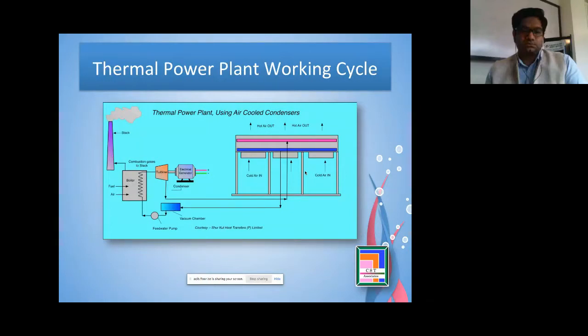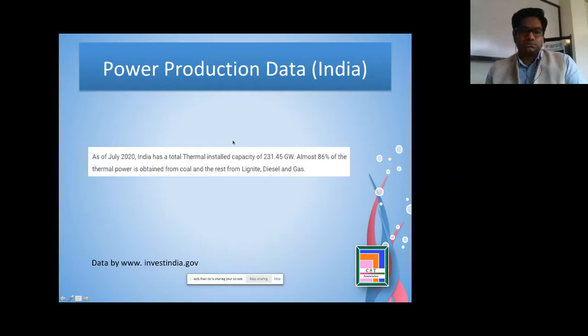And the second system is in countries where ambient temperature is low, people use air cooled condensers. The process is the same. Instead of steam going to the cooling tower, it goes to the air cooled condenser. The air cooled condenser condenses the steam and it goes back to the vacuum section, and from the vacuum chamber, it goes to the feed pump and then back to the boiler. And the cold air, which is sucked by these fans, transmits the heat, and this is the process which works over there. We will discuss all these methods in detail in the coming slides.